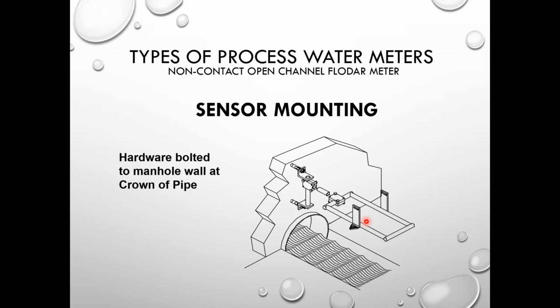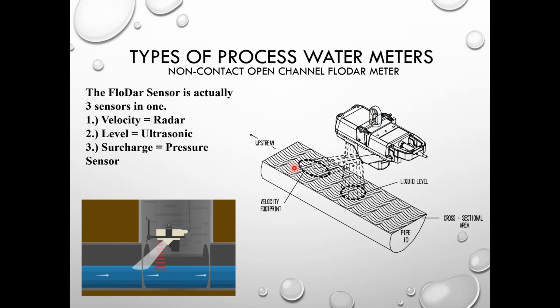So this kind of shows basically a way of mounting that sensor to the wall over the crown of the pipe. It's just simply 2 bolts, and you mount this frame assembly to the wall. It measures, again, velocity with the radar horn and ultrasonic for level depth. You want to have it facing the flow so that the water is flowing this direction here and out. So as water is flowing across, it's shooting the velocity here at the invert of your pipe, and then you measure from the top of the pipe down to the surface of the water to calibrate this instrument. As the water comes up over the top of the sensor, it has a pressure sensor that's up in the unit housing itself that will monitor liquid depth above the top of the sensor.